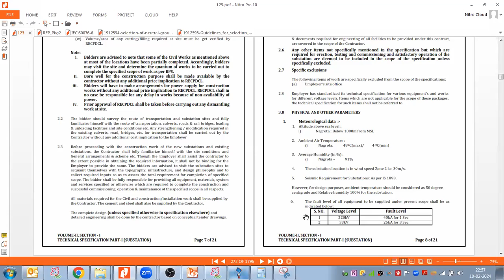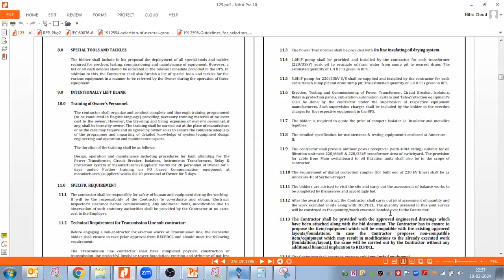Here you can see your fault level is given. So when you are designing, you make sure for 220 kV it's 40 kilo-amps fault current, for 33 kV it's 25 kilo-amps for the same fault current. So one thing you check is your fault rating here. I will take this fault rating in my next class. They have given the drawing directly here as well.